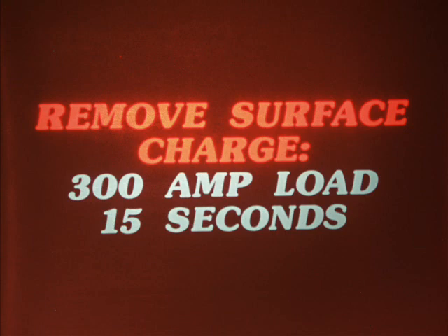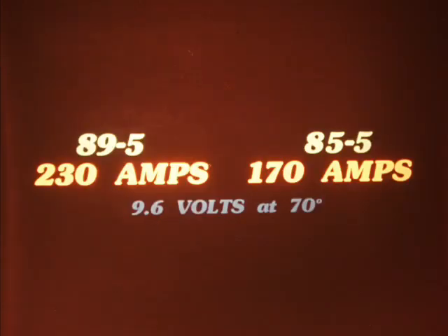To load test the battery, first connect a 300-amp load across the terminals for 15 seconds to remove the surface charge. Then, reduce the load to 230 amps for Model 89-5 or 170 amps for Model 85-5 for 15 seconds and read the voltage under load. It should be at least 9.6 volts at 70 degrees ambient temperature, or as specified in the maintenance manual for lower temperatures. If the voltage is up to specs, the battery is okay. If it's below specs, replace the battery.